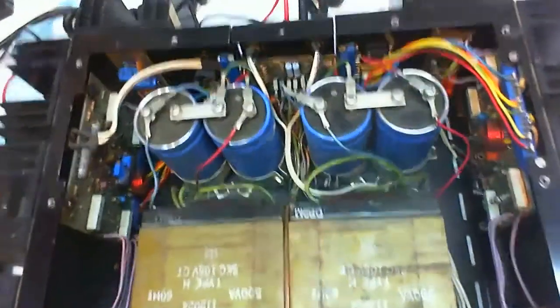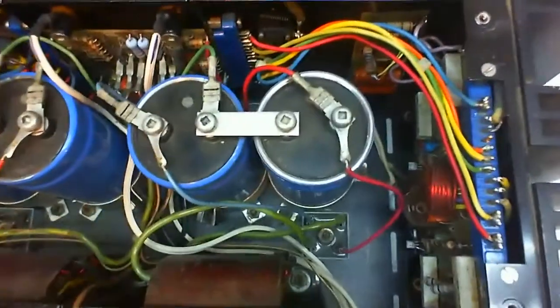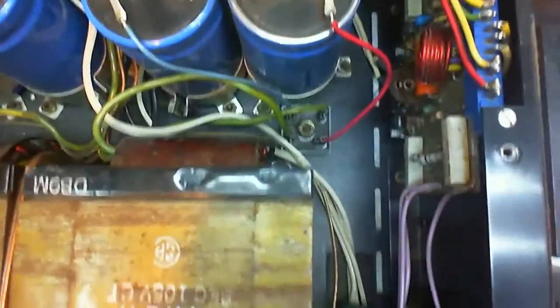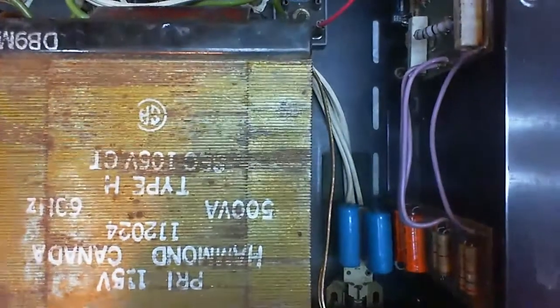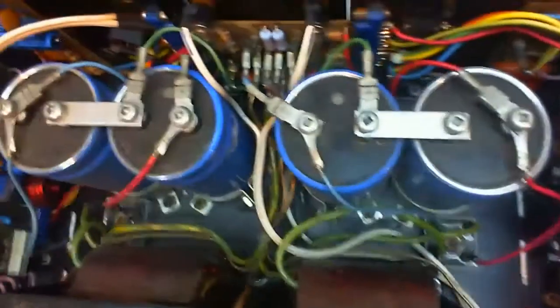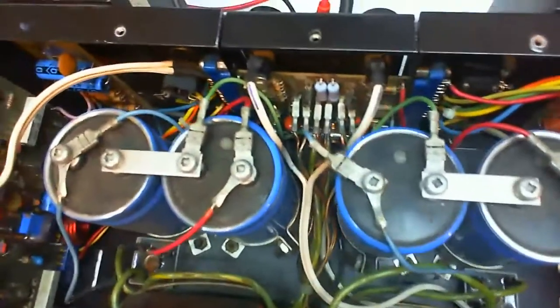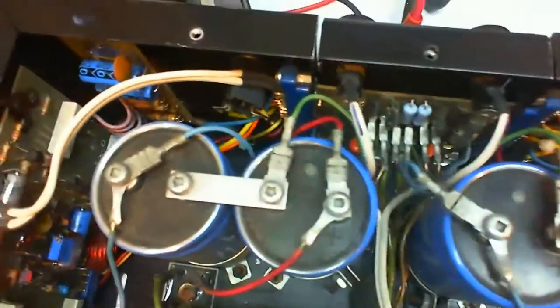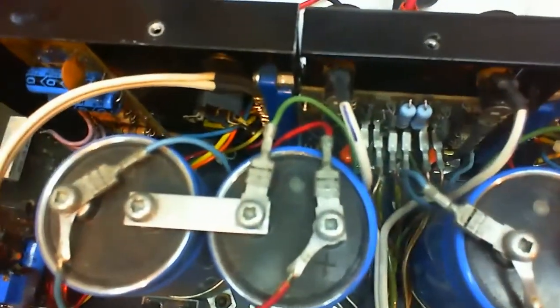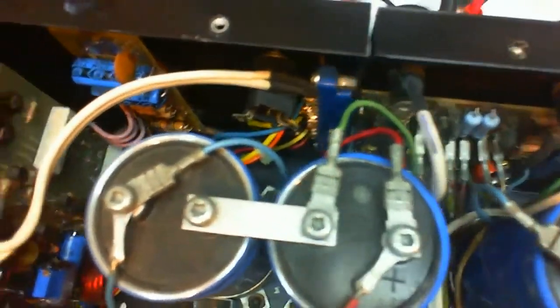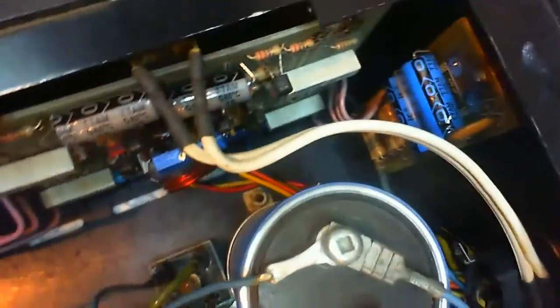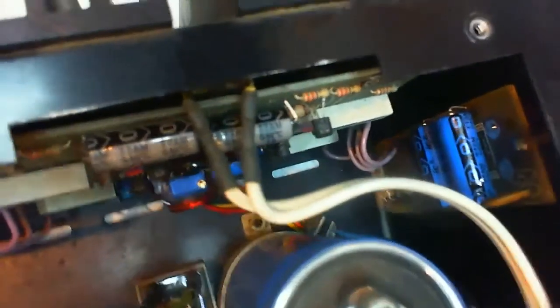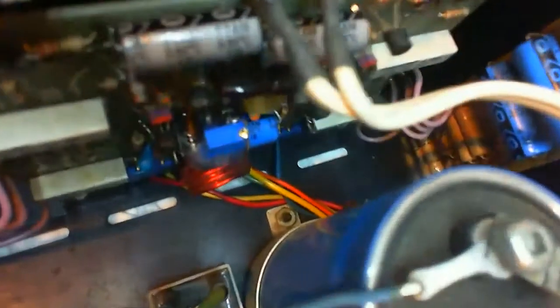So that's the whole amplifier with the repaired module reassembled. The module to the right I didn't touch. In the middle we see the four big DC bus capacitors. And to the left we see the repaired module with the electrolytic capacitors that we replaced and the little blue trim pot, which is a multi-turn trim pot.